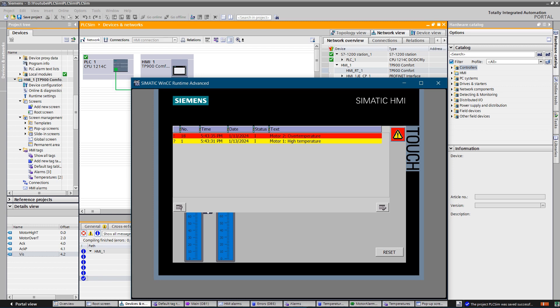Error is activated when motor reaches temperature of 90 degrees Celsius. On error, operator gets a different message on actions needed to be taken into account compared to warning. If error occurs, motor will be stopped to avoid further damage to the equipment.